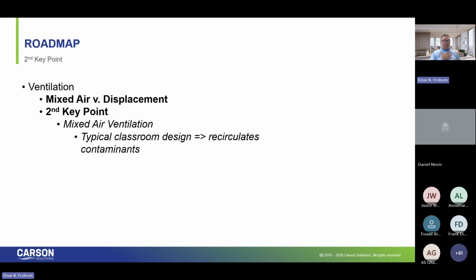And picture this. If I'm a third grader, and the predominant way in which viruses transmit is airborne lingering particles, so it's not fomite, not surface pickup. I'm not advocating going and licking doorknobs. I'm not. But the lingering particles that are airborne are the predominant way in which people get infected and then become sick. So if I come to third grade and I've got a virus and I exhale, the natural tendency is that those exhaled contaminants are going to be about 95, 96 degrees. They're going to be warmer than the air in the room, more buoyant, and they're going to want to go up. And think about an air handler VAV arrangement or any type of in-ceiling diffuser. What is that going to do? It's going to push that air back down to the other occupants in the space. So we're not doing a good job of getting rid of contaminants in a mixed air environment.